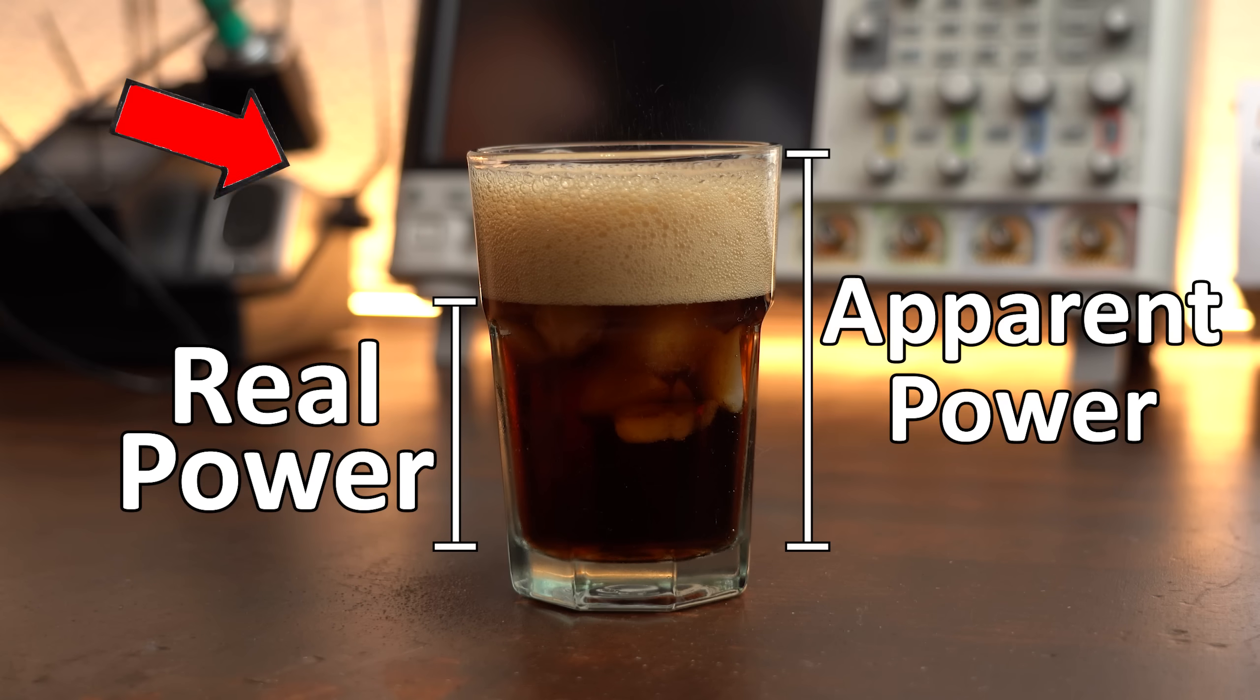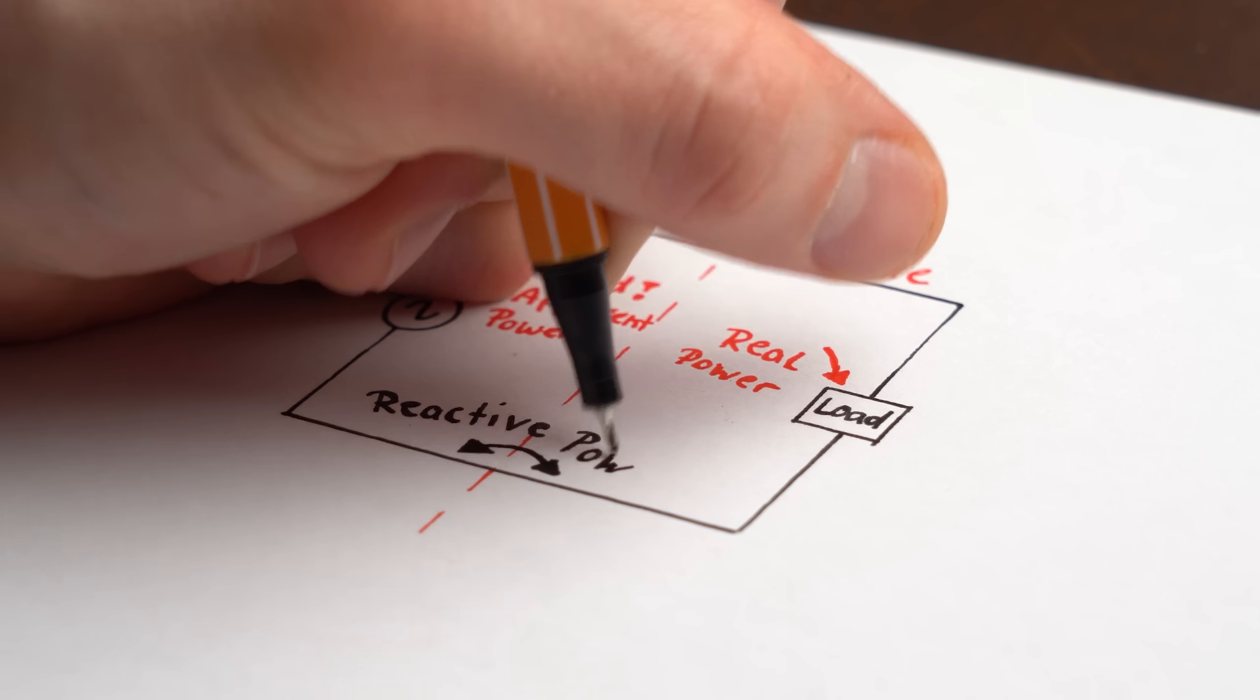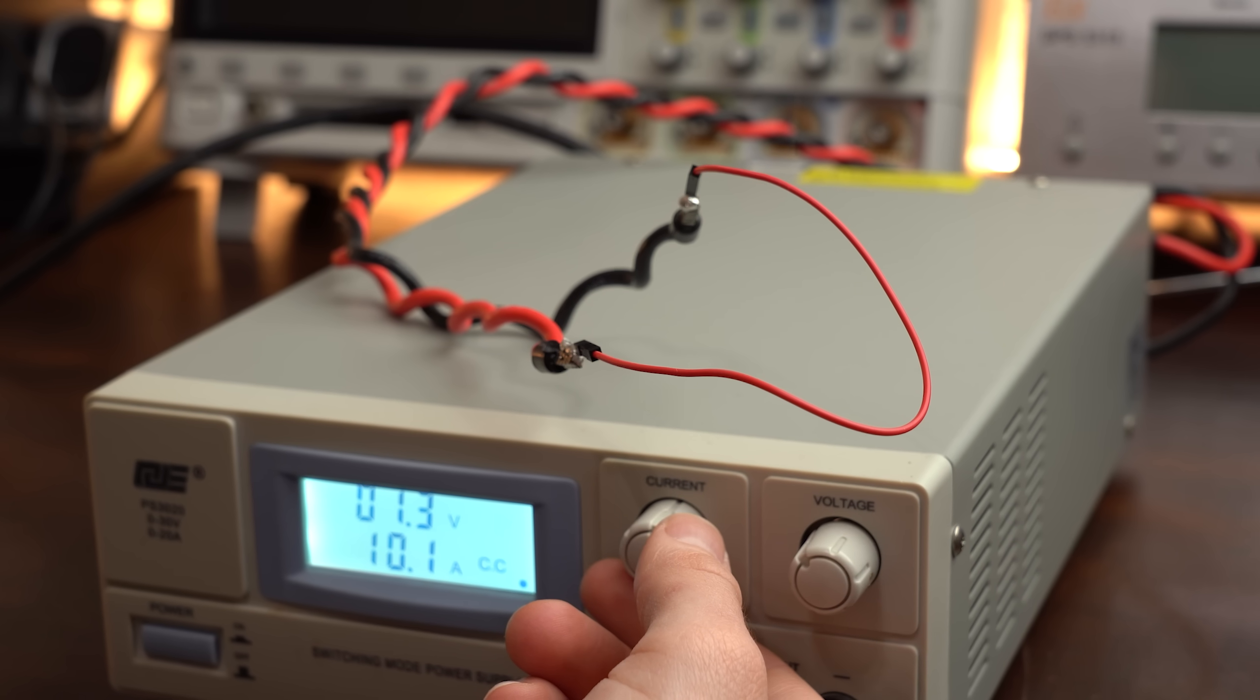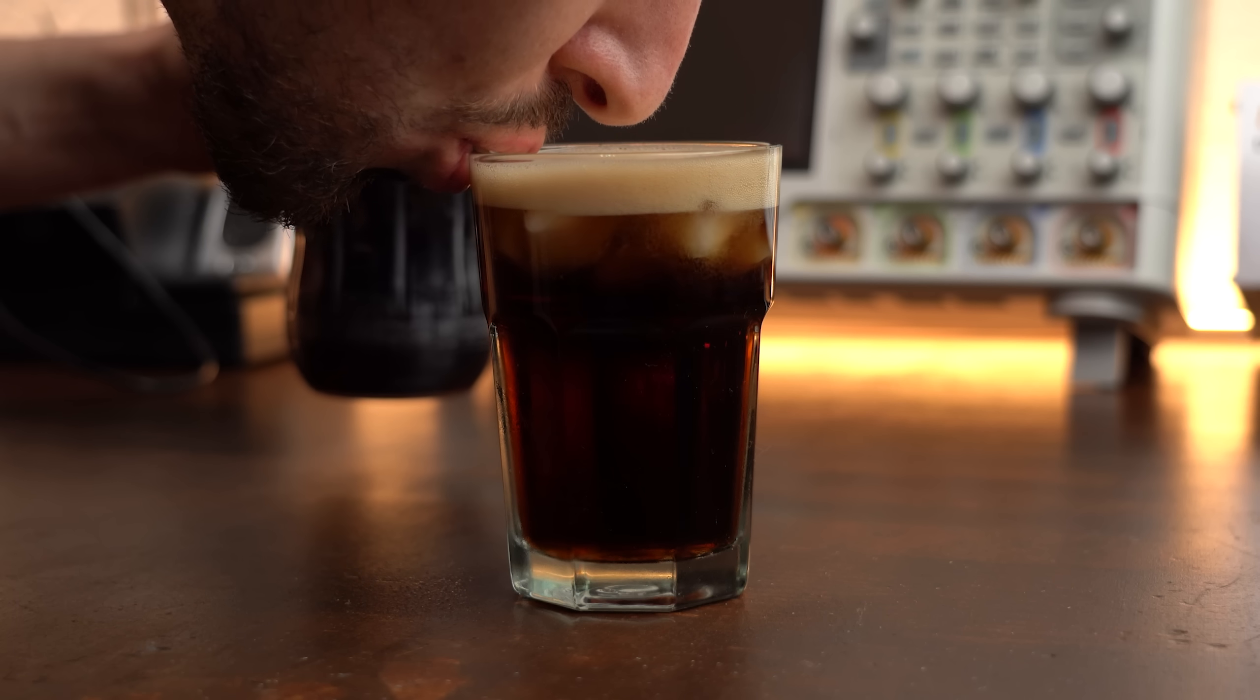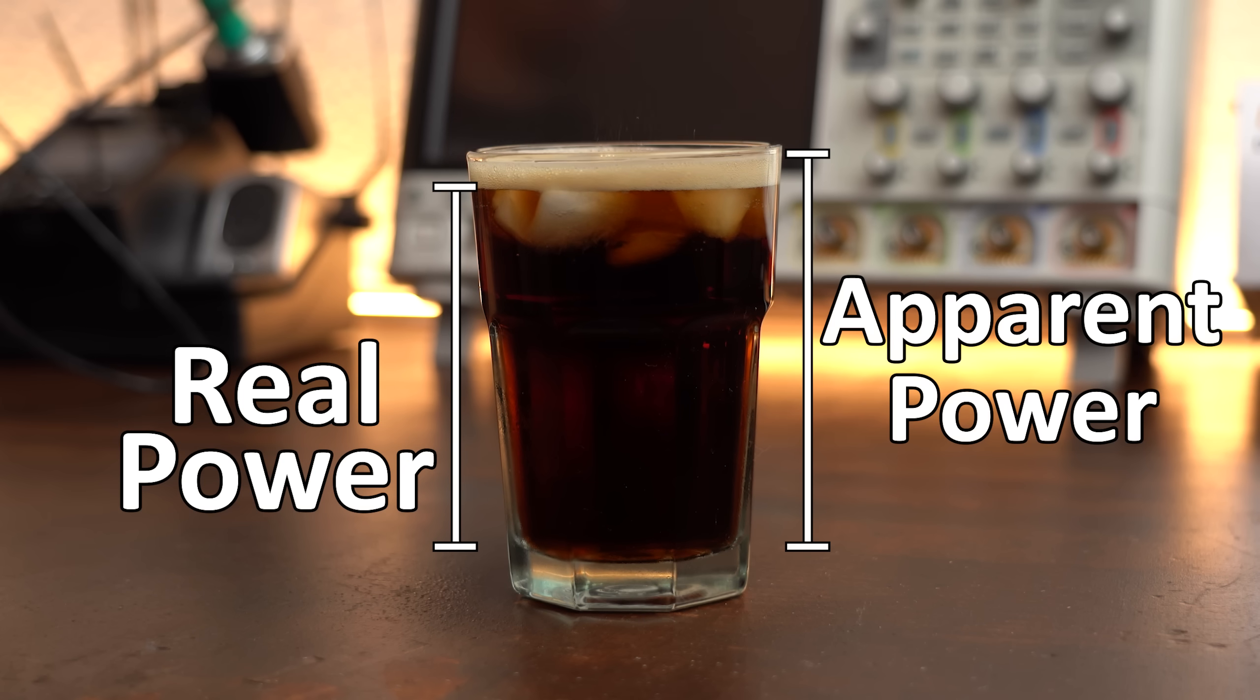No, we still got the foam which is our reactive power and truth be told completely useless because it only oscillates between the energy provider and hooked up loads. Due to it more current flows through the grid than what we actually need for the real power demand and as you might know for bigger current flow we need thicker wires so that things do not get terribly inefficient and hot and that of course costs lots of money. So keeping the reactive power close to zero is our goal here meaning that apparent power should equal the real power.